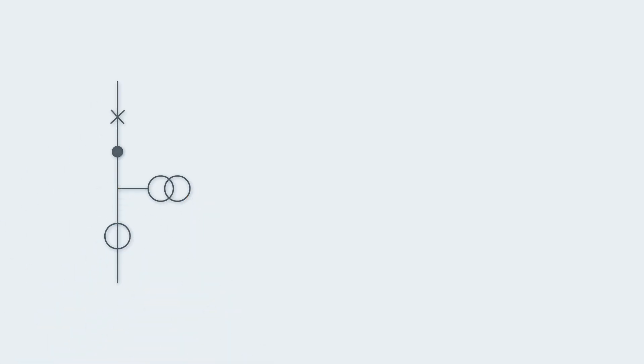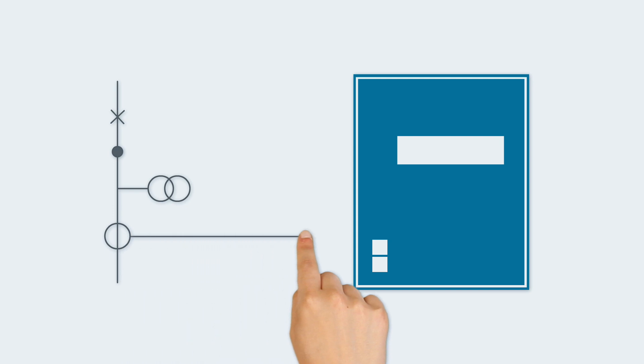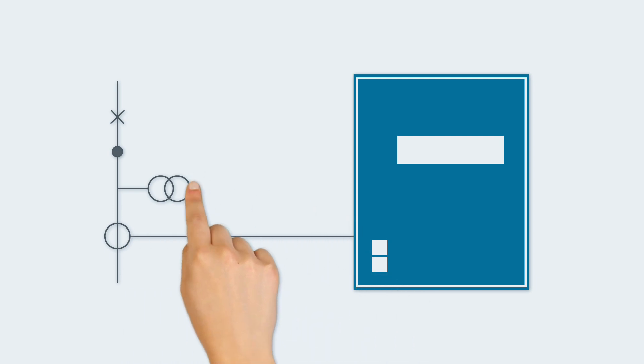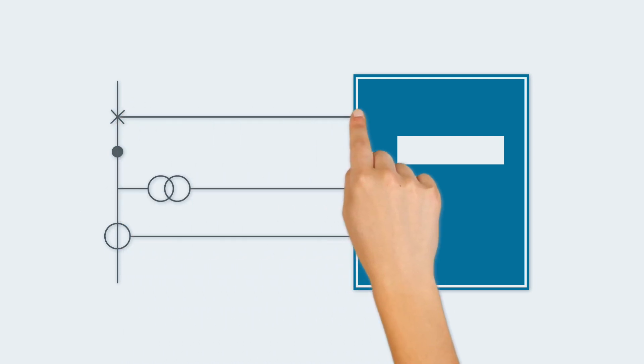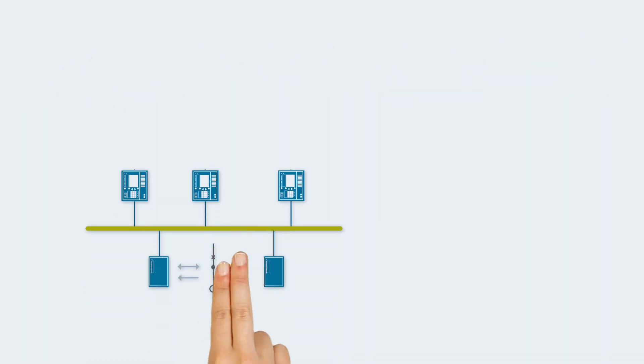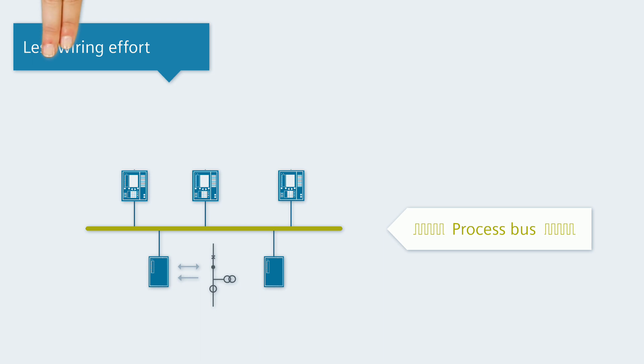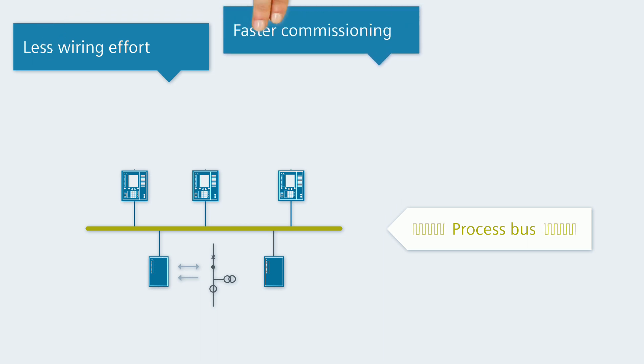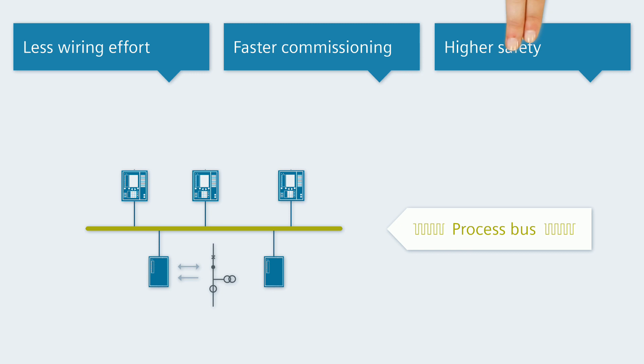Switching devices and instrument transformers are traditionally wired directly to the protection device. Our tip? Break with tradition. With a process bus you achieve the same goal, and that with less wiring effort, faster commissioning and higher safety.